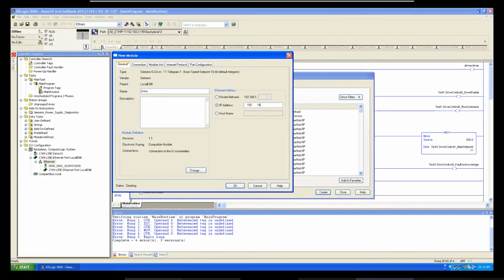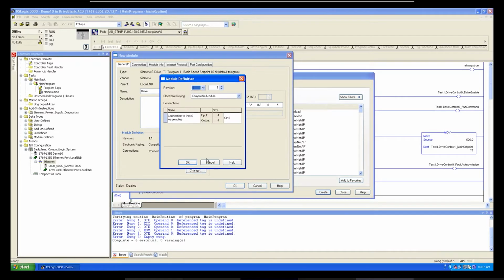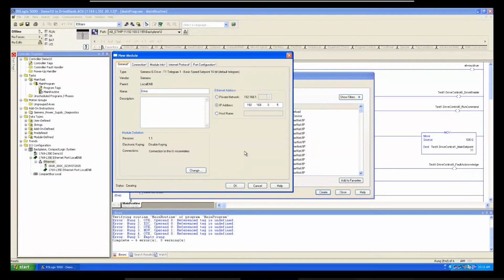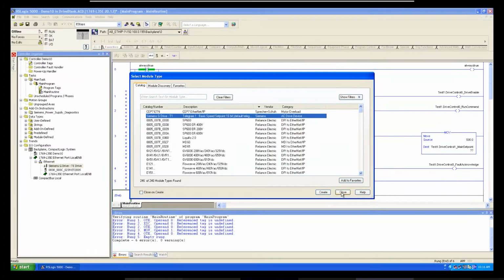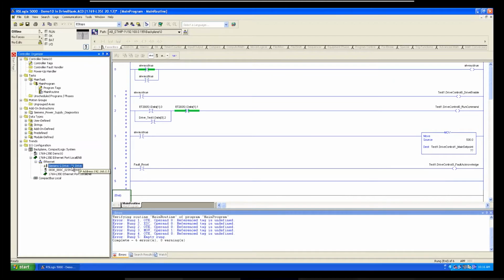And put in the IP address. We do need to change the keying and the data layout here. By default, it does not disable the electronic keying. We need to do that. And we need to change the data layout from SINT to INT. Hit OK. Yes, we want to change the module definition. OK, and close. All right. So now we have the drive.